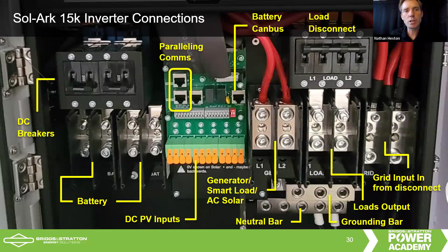Those are DC breakers on the positive poles coming in. You can use that as your combiner for up to 2 stacks, right? So if you've got 2 battery inputs, you can use those DC breakers as a combiner, those dual DC inputs. They do combine to a common DC bus right after those fuses. You've got your solar inputs for DC solar. You have 3 independent MPPTs, 2 strings per MPPT.